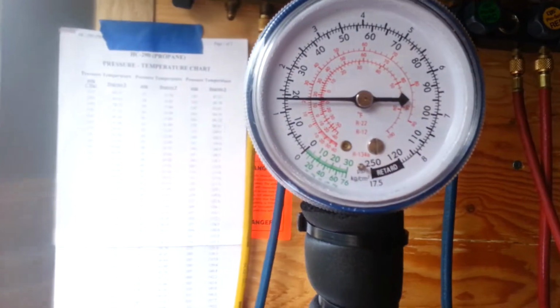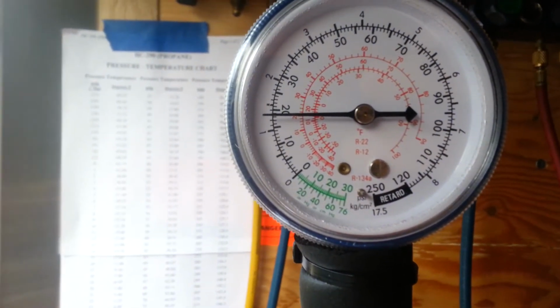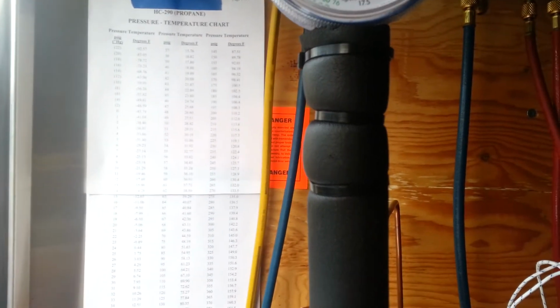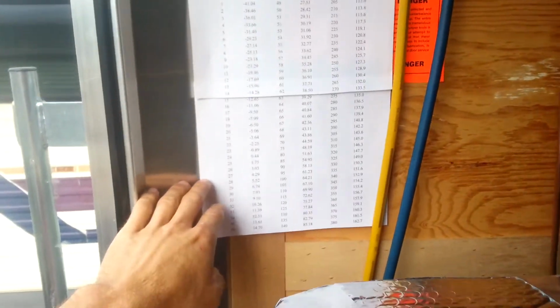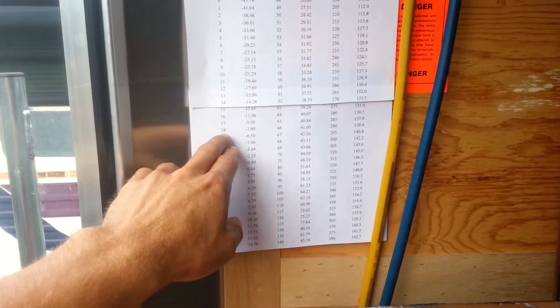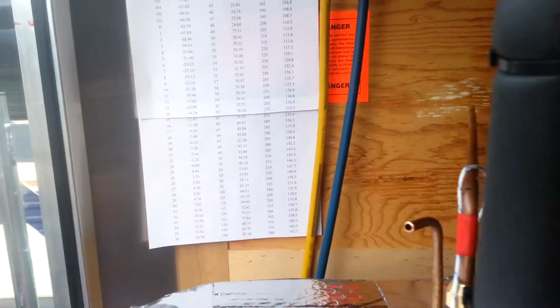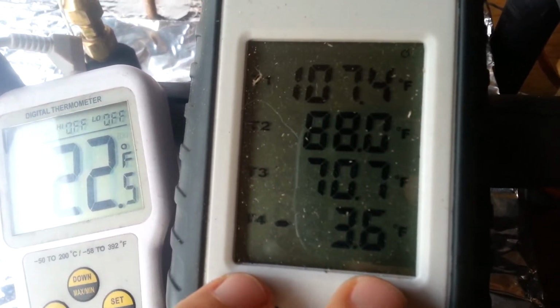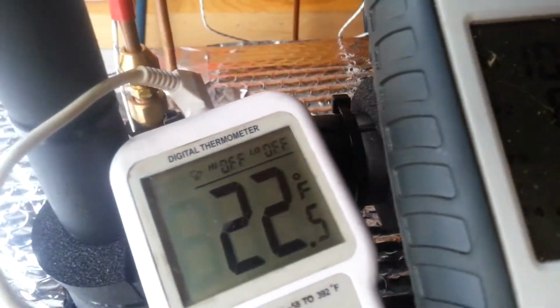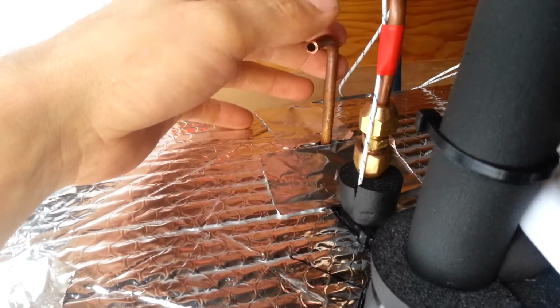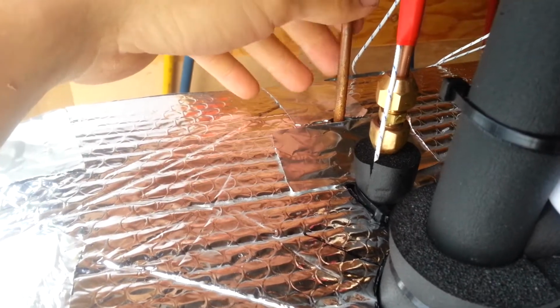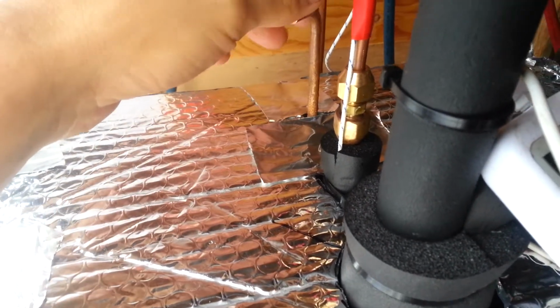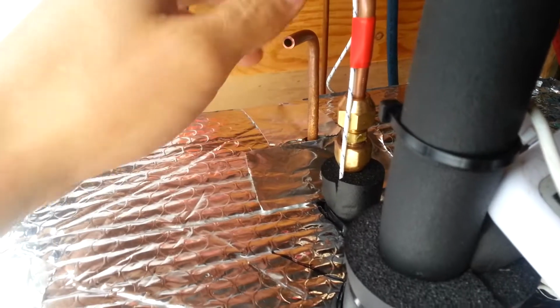And speaking of the suction temperature, I thought I would demonstrate something here. Kind of neat. So we've got about 19 pounds per square inch, 18.5, 19. So we refer to our table here. We're talking somewhere between 6.5 and 8 degrees below 0 Fahrenheit. And if you observe this last value here, it's negative 3.6 degrees Fahrenheit right now. Now, something kind of fun with this: if I vary the throttle, this is my control for the throttle, it's a needle valve down inside this box. This allows me to control it from the outside without having to open up the box.